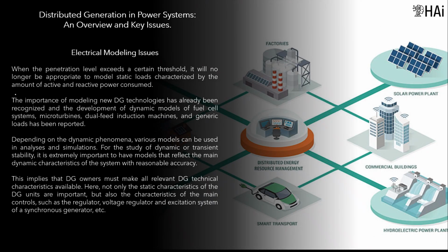Electrical modeling issues. When the penetration level exceeds a certain threshold, it will no longer be appropriate to model static loads characterized by the amount of active and reactive power consumed. The importance of modeling new DG technologies has already been recognized and the development of dynamic models of fuel cell systems, microturbines, dual-feed induction machines, and generic loads has been reported. Depending on the dynamic phenomena, various models can be used in analyses and simulations. For the study of dynamic or transient stability, it is extremely important to have models that reflect the main dynamic characteristics of the system with reasonable accuracy. This implies that DG owners must make all relevant DG technical characteristics available. Here, not only the static characteristics of the DG units are important, but also the characteristics of the main controls, such as the regulator, voltage regulator and excitation system of a synchronous generator, etc.